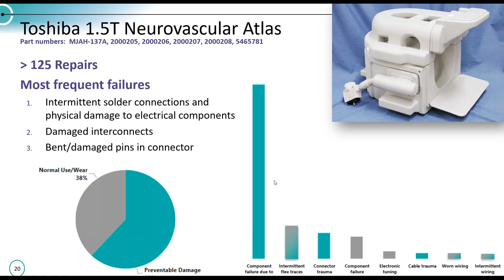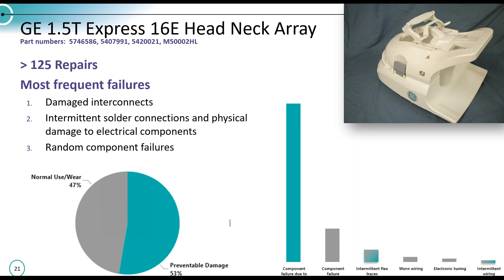Another type of head coil that we see a lot of is a GE head and neck array. Again, a multi-piece design. So the patient lays down, the top part of the coil is then placed on top of the patient's face and head and snapped together to the bottom modular section. With that, we see a lot of damaged interconnects, and I'll talk about why this might occur later on in the presentation. But we do see a lot of physical damage to either interconnects or the connections between the various pieces, and then also the intermittent solder connections. And then thirdly is just random component failures.